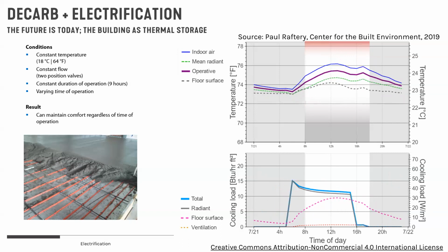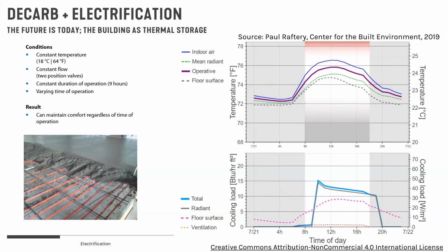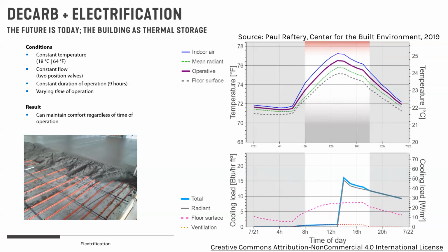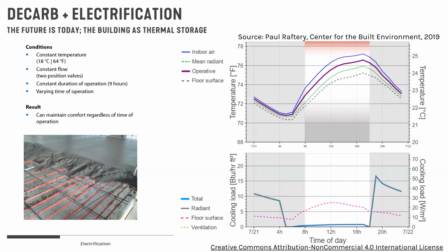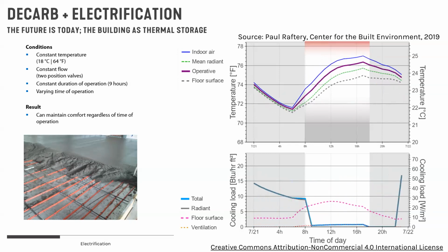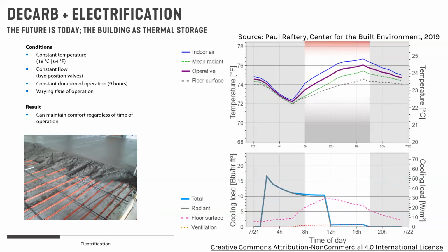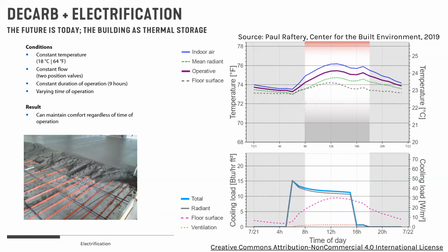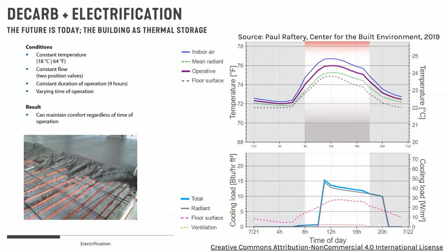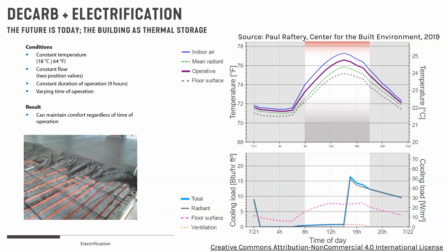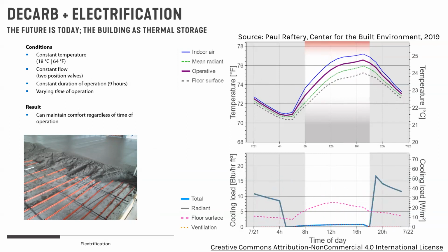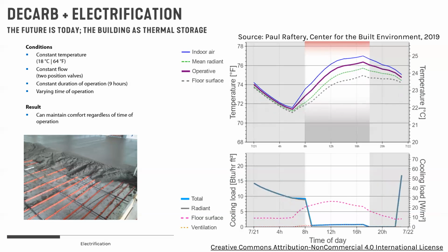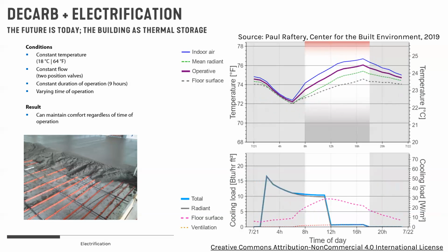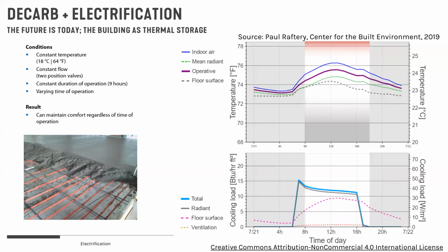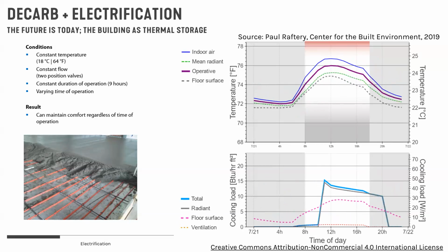Imagine a building that's 100% glass with just dual-pane glazing and no shading in a very hot climate: you will likely exceed the cooling capacity of a radiant slab. So we can't ever think about these systems independently; the building envelope and the mechanical system have to pair well. But that load-shifting capacity is very flexible in mass buildings.